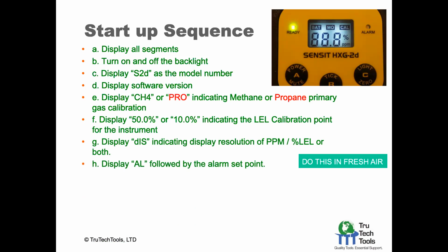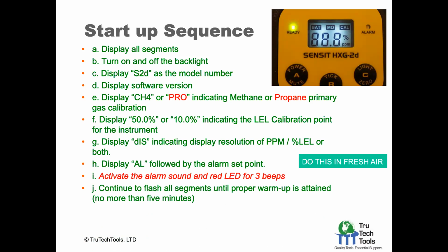Then next will be the alarm set point. And then the alarm will actually sound itself to make sure it's working, and the red LED will flash, and you'll hear 3 beeps to let you know that the alarm is in effect working as it goes through its startup cycle. They'll continue to flash all these segments until the warm-up is final and attained, and that's usually no more than 5 minutes. And if you are zeroing it, it'll come up with 0, indicating fresh air zeroing. And then the full working display is shown at the end of the sequence.